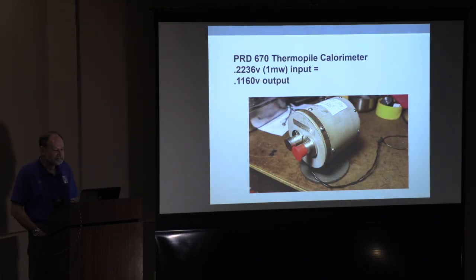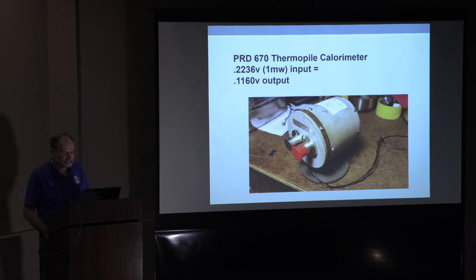Here we are, the PRD 670 thermopile. And it's exactly what it looks like. There's an N connector, you put the power in up to 100 milliwatts. There's a temperature compensating thermopile and DC leads that come out the back. So you put in 0.2236 volts, 1 milliwatt at 50 ohms, DC into the RF input, and the output is 0.1160 volts. So if you put 1 milliwatt at 30 megahertz in, you should see 0.1160 volts output. You could probably get more resolution, but unfortunately, everything disappears into the noise after the 0.1160 volts. I don't get a stable enough reading to make it worth it. Some digital averaging or something might give me one more digit. But this is basically a calorimeter where heat is used as a transfer medium between RF and DC.